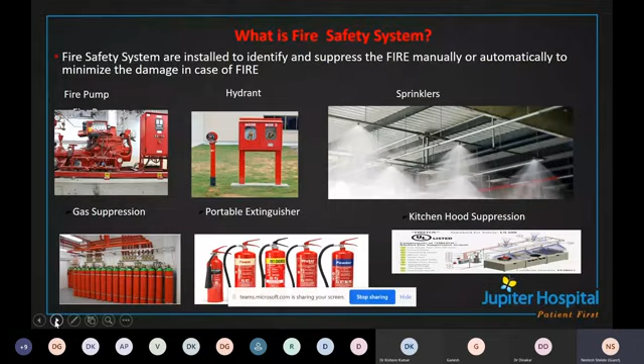And if the sprinkler becomes active in a kitchen area where oil is present, it is more dangerous. So a special type of detector is used in kitchen areas, with hood suppression. This is the ideal way for the kitchen, with a UL listed vendor. Now if you see the kitchen fire suppression system here, you can see the utensils, and exactly on top of them is a hood, the exhaust hood, which takes the smoke and heat created there to the outside.